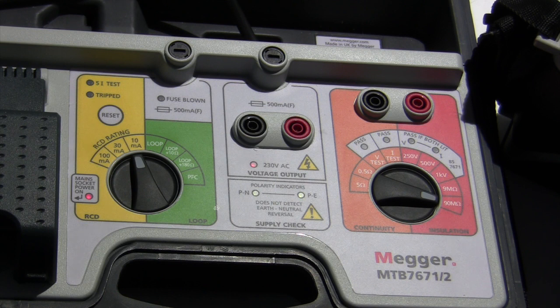happens to have an open day when they are offering calibration services, and it happens to be calibrated usually by some sweaty bloke sitting in a hot non-climate controlled office out the back there, where the tester's just come off the van, hasn't had time to acclimatise, and they just run it through whatever tests from whatever tester that they run it through, and at the end of the day I get a certificate with their signature on saying that it's all good and above board, which is fine because it shows I've done my due diligence, and it keeps the likes of NICEIC happy when they come to audit me.